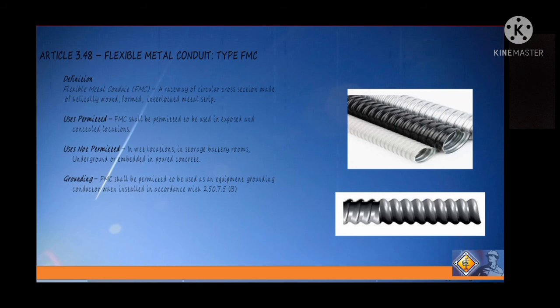Next in Article 3.48, which is the flexible metal conduit or the type FMC. For definition, FMC is a raceway of circular cross-section made of helically wound, formed, interlocked metal strip. So makikita natin sa right side ng ating slide ang ating type FMC or the flexible metal conduit. In terms naman of uses permitted, FMC shall be permitted to be used in exposed and concealed locations. In terms of uses not permitted naman, hindi siya pwede sa wet location, in storage battery rooms, underground, or embedded in poured concrete.